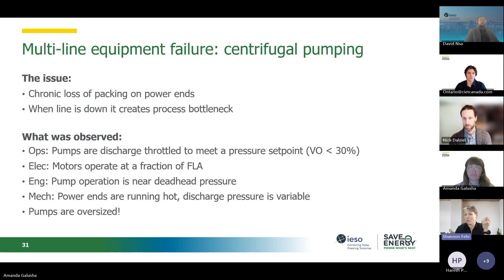So what can we do about it? That's the next slide, Amanda. So this is a nice pictorial description of the system I'm talking about. It was 2 large cleaner feed pumps with discharge throttled valves to meet a pressure set point. And they actually had a crossover line with an isolation valve. So there were quite a few configuration options. Looking at the curves, you find out that you can actually operate one pump to feed both lines.